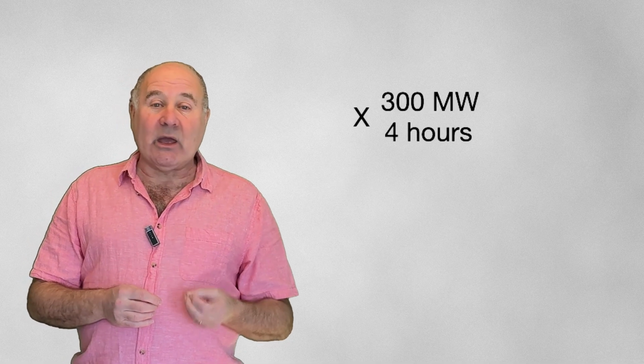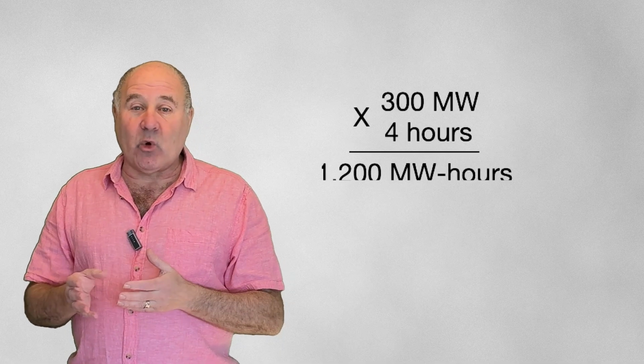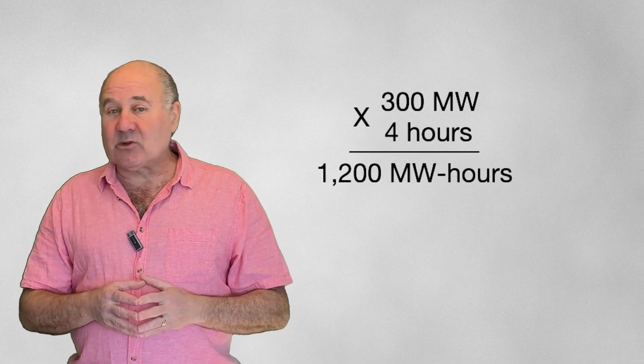Grid scale batteries are typically rated in power output and the duration which they can run at that power. So a 300 megawatt, 4-hour battery can store 300 times 4, or 1,200 megawatt hours of energy. And you need to put even more energy into the battery, since some is lost during the charge-discharge cycle. Thanks for sitting through the boring part, because you need to understand that for what comes next.